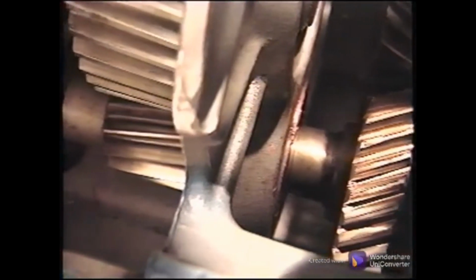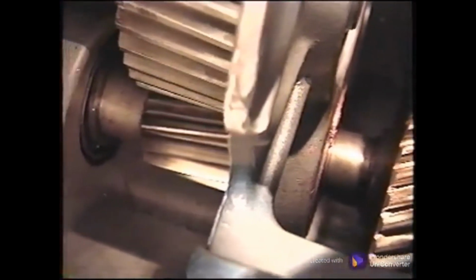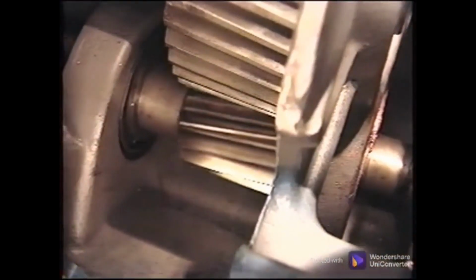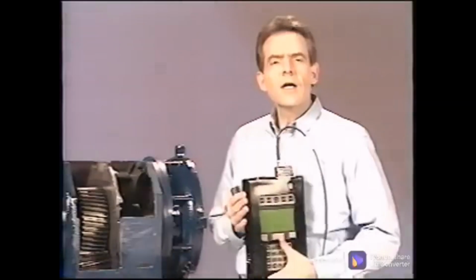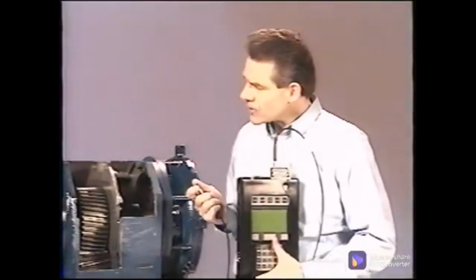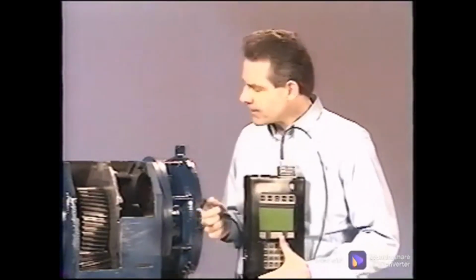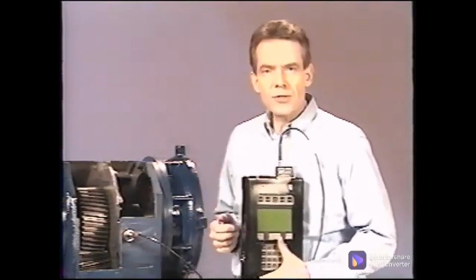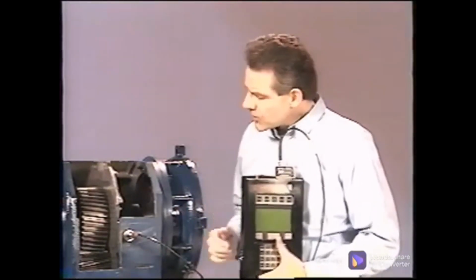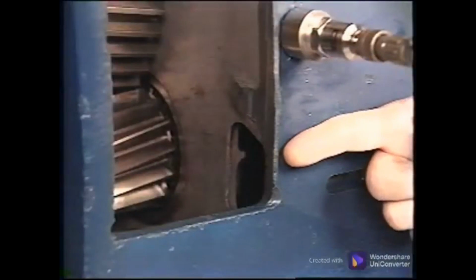Remember that shaft vibration, including gear vibration, is transmitted through these bearings and mountings to the case. It is important to know the internal design of the gearbox to accurately place the sensor on a web reinforcement which transmits the vibrations best. If possible, stay away from voids or hollow castings.